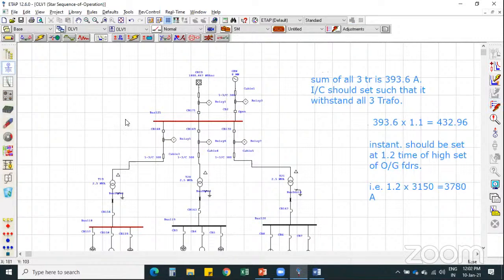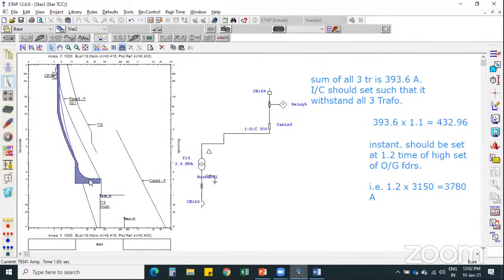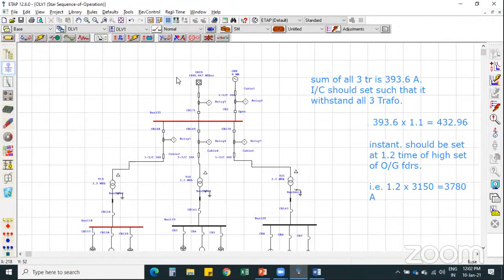So similarly, we can set for other relays also, and the same philosophy has been adopted for this relay setting calculation. While calculating, one must see these curves such that they do not get overlapped. This relay should not get overlapped. Here you can see the whole network.